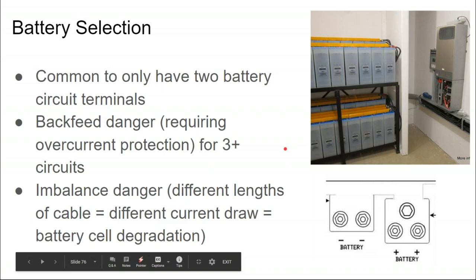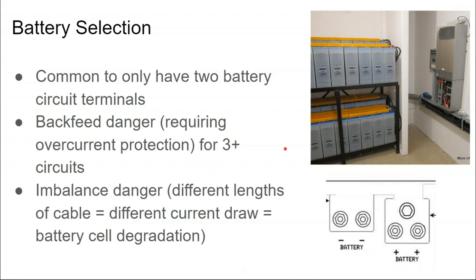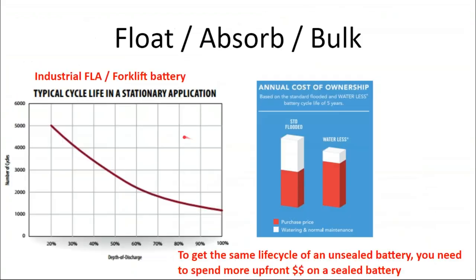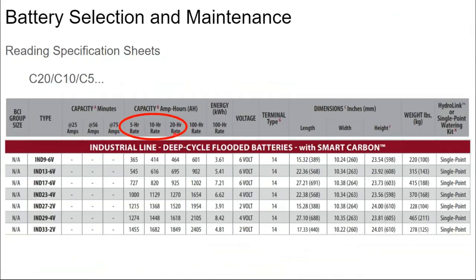So you're looking at 3 kilowatts for 5 hours, which is 15 kilowatt hours at a high rate of discharge. If your loads are going to be larger than that, you need even more batteries, and you might have to select a costlier battery.